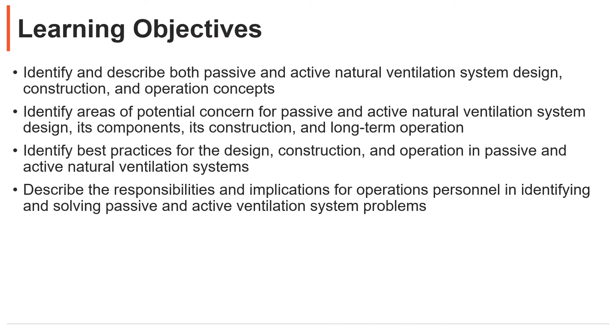The driver for natural ventilation design and passive cooling is energy reduction. In our climates here in Seattle and Portland, we have ample opportunity to use this as a resource in design. The concept is to decrease your conditioned airflow into a building, potentially disabling it, and bringing in the right temperatures directly into the room, like your economizer function. This can really reduce fan power and mechanical cooling and heating, since it can be used for passive heating as well in the right climates and conditions.